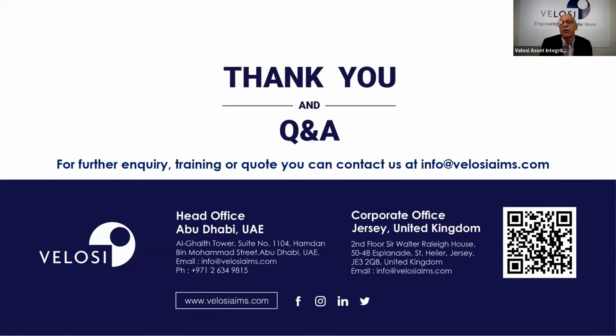You can get it. However, if you want to have a proper system, because the machines are critical, you can also talk to your manufacturer of the machine, or OEM, about what alternative solution they may recommend. We talk to them, but still they prefer, even the client is preferring, the Bentley Nevada. The issue is the delivery. The compressor delivery time is 8 months, and the Bentley Nevada is coming after 12 months. So yeah, these are challenges.